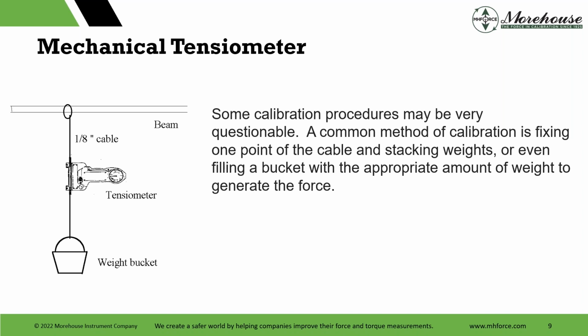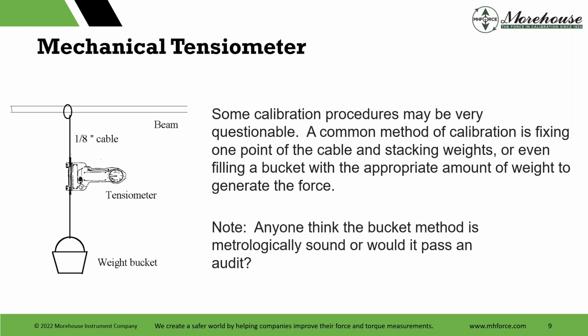Pulled this from the old web. Some calibration procedures may be questionable. Here, when I did a Google search, it said a common method is fixturing one point of the cable and stacking weights, or even filling a bucket with the appropriate amount of weight to generate the force. Now we have all kinds of problems with just filling a bucket with mass, right? Do the correction for density, air, both material and air, do the correction for local gravity if we want to generate a force. There's lots of different things that might be wrong with this method, and we're just going to attach something to a beam in a building and go to it. I don't think auditors are going to like that too much, though you can decide if you think the bucket method would be metrology sound and would pass that audit. I'm saying most auditors are going to say no, though who knows.